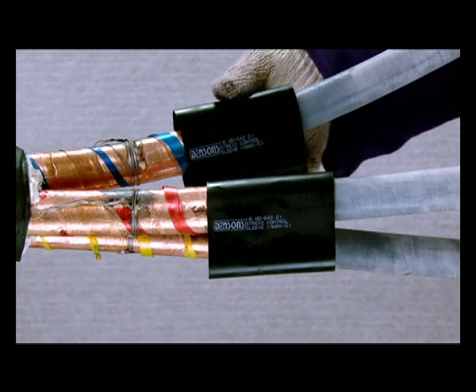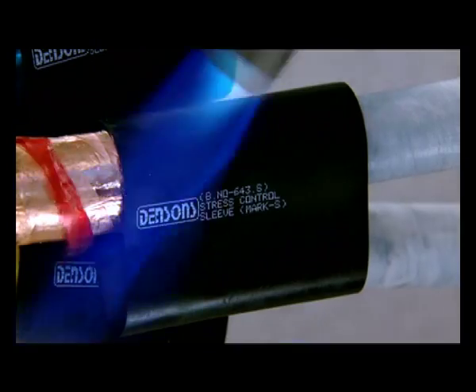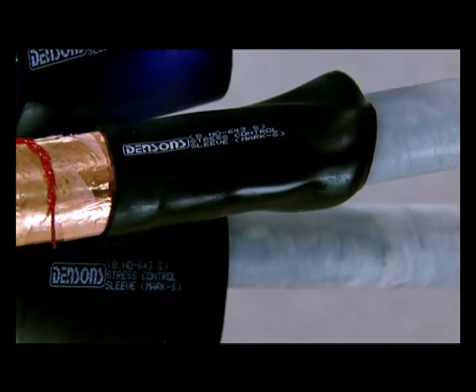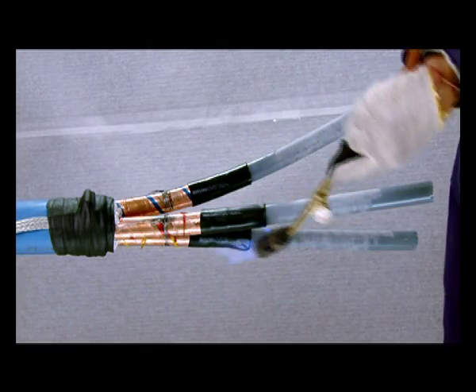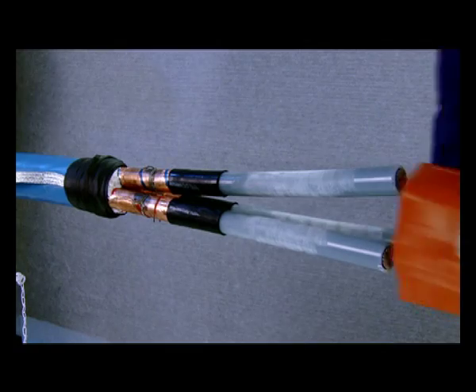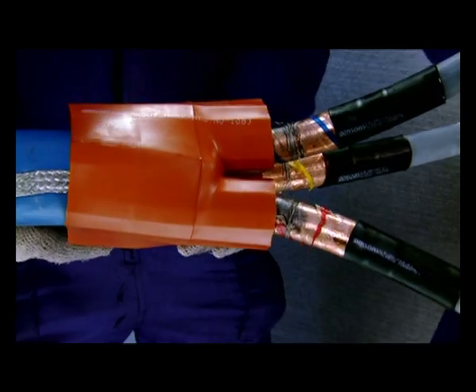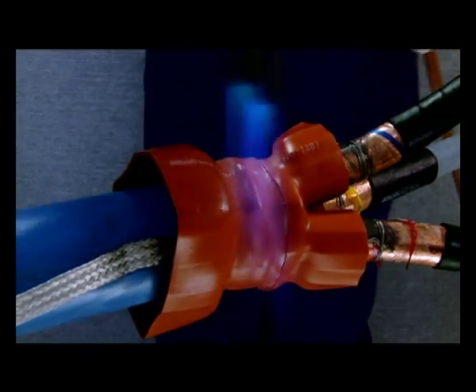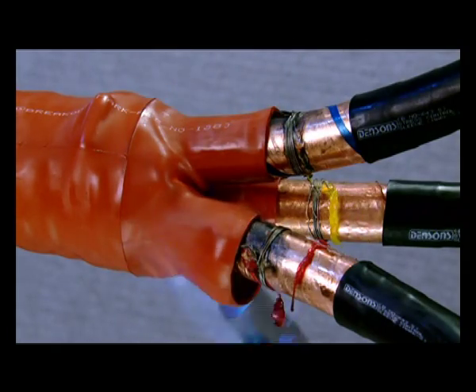Insert stress control tube over one core at 20 mm over the metallic foil. Proceed to insert the stress control tubing on the remaining two cores one after the other. Using a blow torch, start shrinking the tube from the lower end and proceed upwards. Ensure that the tube is shrunk uniformly and is free from voids and wrinkles. Insert the breakout over the cores and pull it down into the crotch as far as possible. Shrink the breakout into place starting at the center, working first towards the lower end and then shrink the fingers onto the cores.